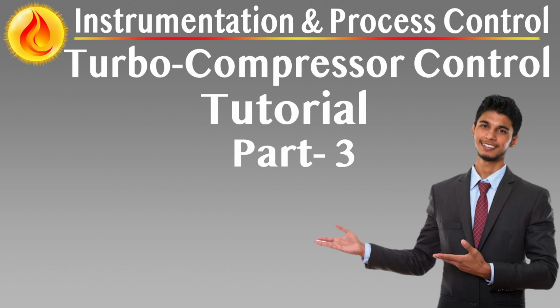Configurable activation threshold. The override controller continuously monitors system pressure. When the measured value exceeds the override set point, it temporarily takes precedence over the normal performance controller. It acts immediately to reduce load and bring the pressure back within acceptable limits. Speed set point override mechanism. The controller sends a revised lower speed reference to each turbine governor, reducing compressor output and system pressure accordingly.